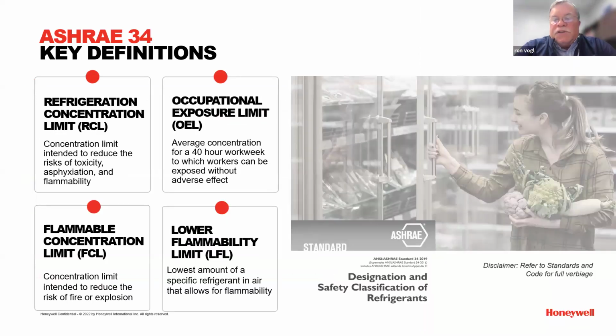There's a couple definitions you're going to have to be aware of down to technician level, and the most common is LFL, lower flammability limit. The reason you need to know that is because all these A2Ls are slightly different and will have a different LFL, even for residential air conditioning, it'll come in the manufacturer's startup instructions.